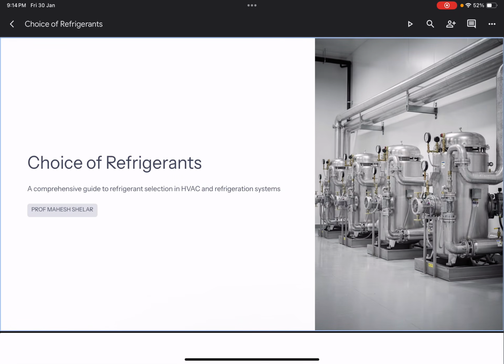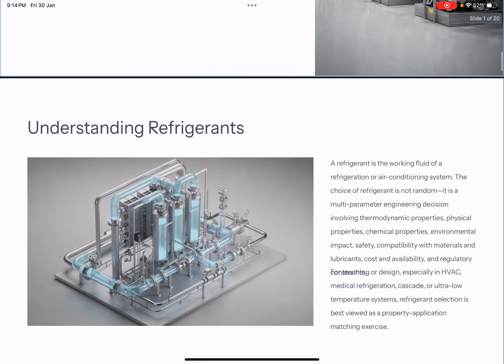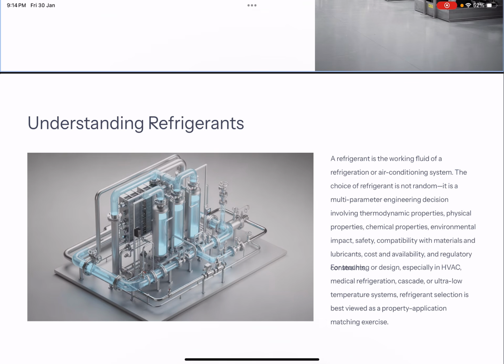We plan to discuss the choice of refrigerants, also called selection of refrigerants, in HVAC and refrigeration systems. We have already defined refrigerants as an important working fluid used in both refrigeration systems as well as air conditioning systems, and it performs a key role in cooling the space by extracting the heat from the space to be cooled in the evaporator of the refrigeration system.